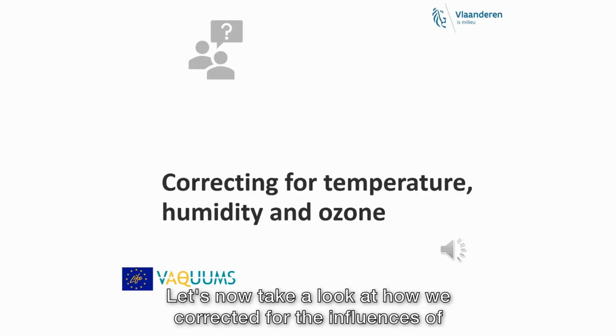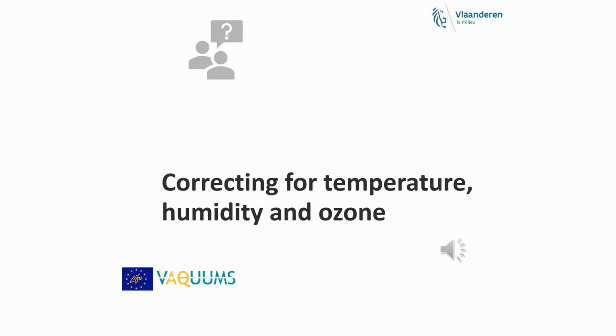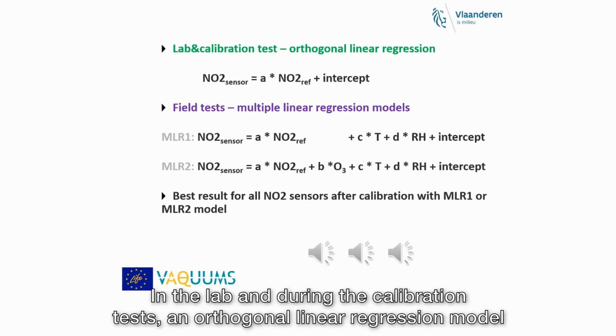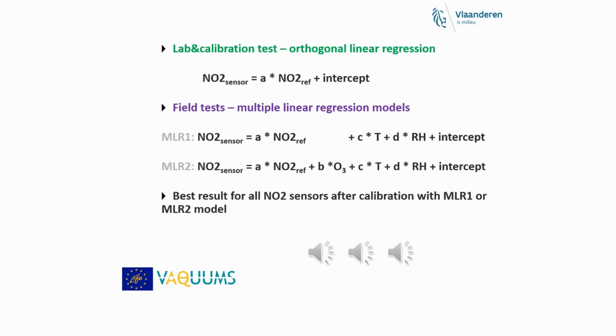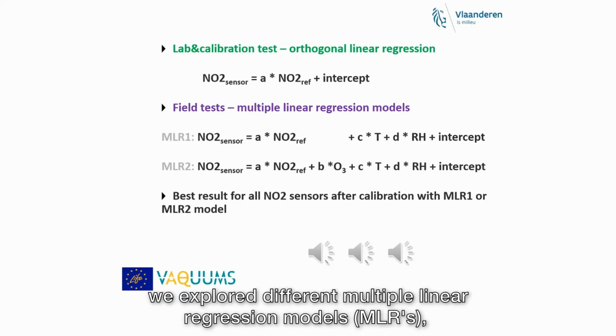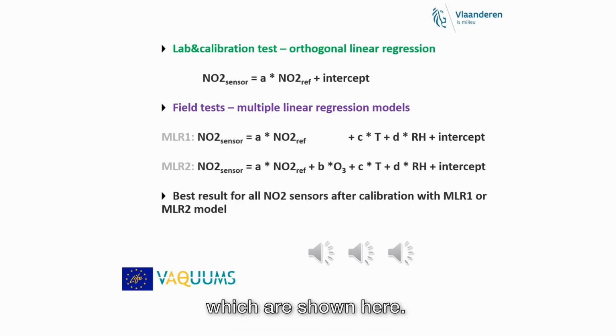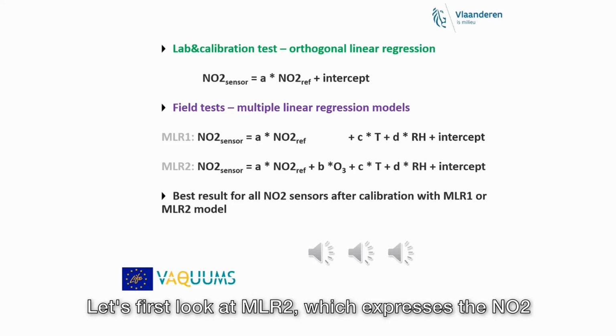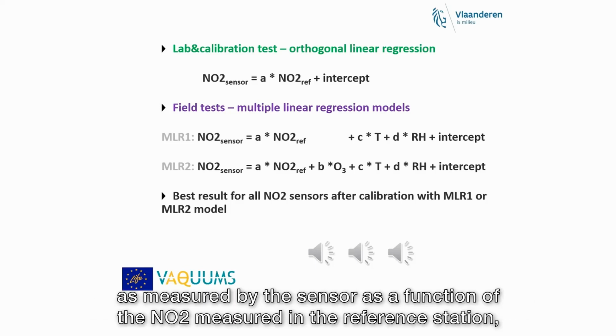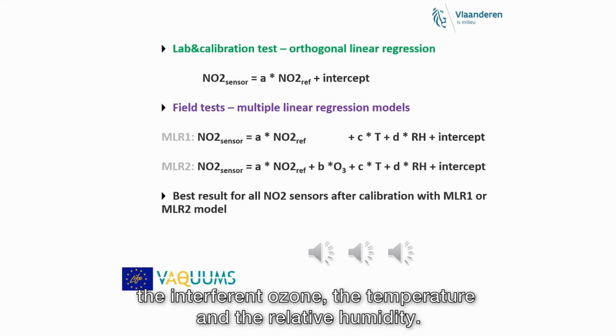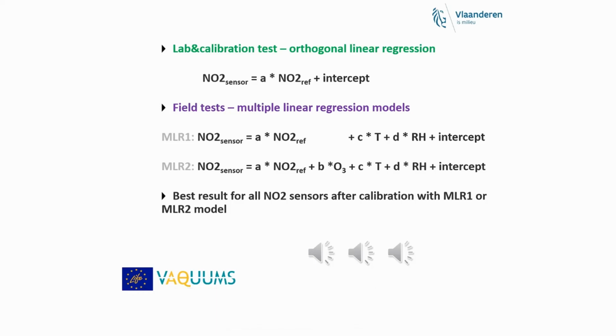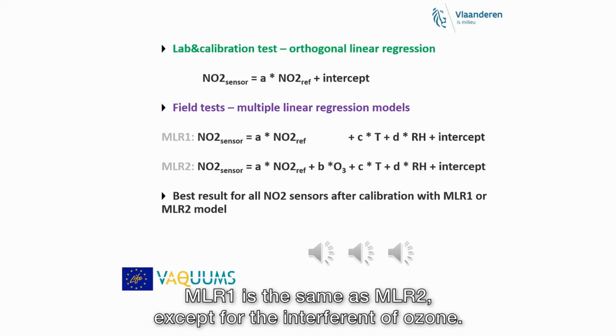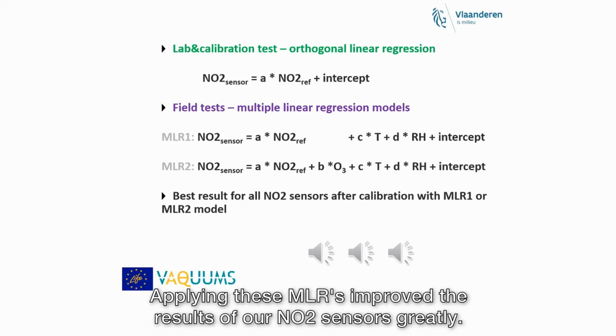Let's now take a look at how we corrected for the influences of temperature, humidity and ozone. In the lab and during the calibration test, an orthogonal linear regression model was used, like the one shown here at the top. During the field tests, we explored different multiple linear regression models, MLRs, which are shown here. Let's first look at MLR2, which expresses the NO2 as measured by the sensor as a function of the NO2 measured in the reference station, the interferent ozone, the temperature, and relative humidity. MLR1 is the same as MLR2 except for the interferent ozone. Applying these MLRs improved the results of our NO2 sensors greatly.